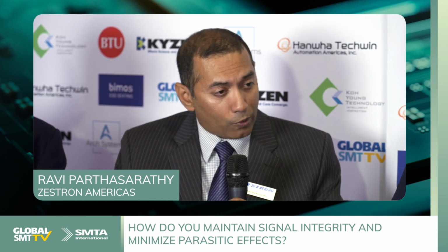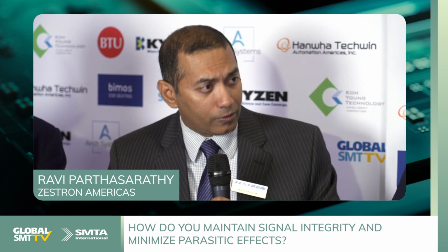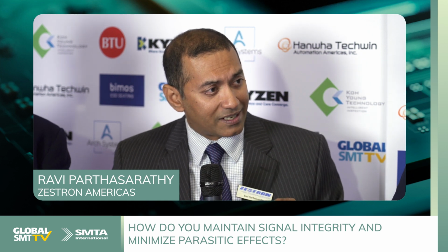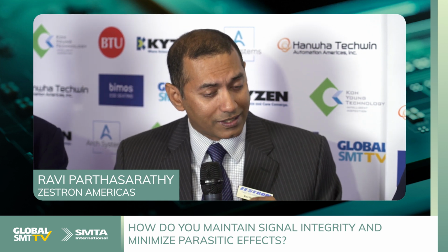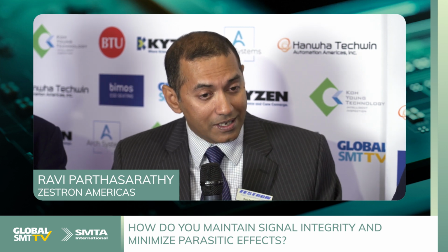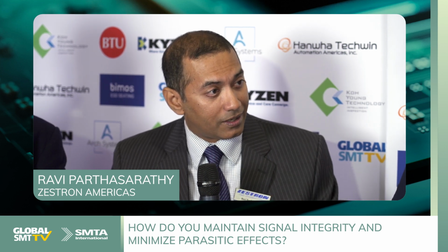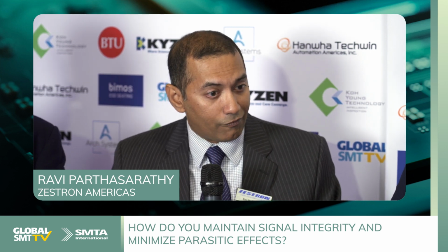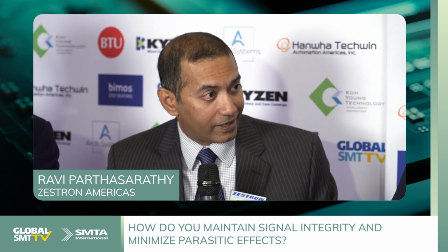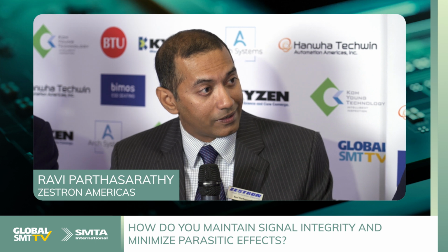Yes. Because even if the board is perfectly clean, with no fluxes or residues, there are plastic materials, there are silicone materials, and if there is even a likelihood of some leaching, that is going to disturb the dielectric values for the liquid immersion cooling fluid, and that could have a significant impact from the heat standpoint.